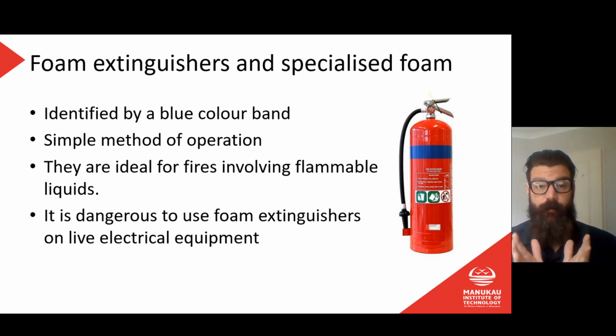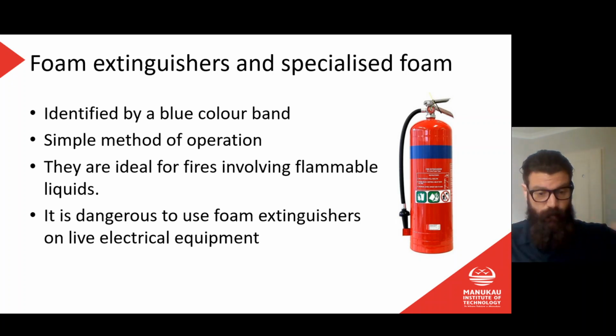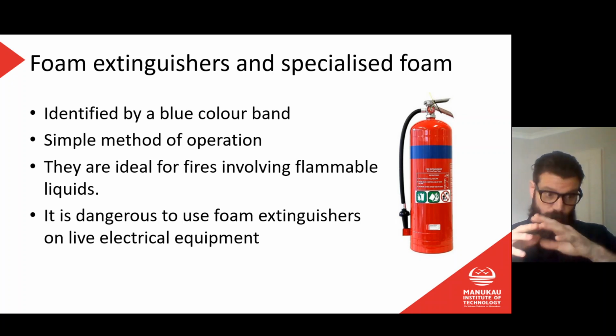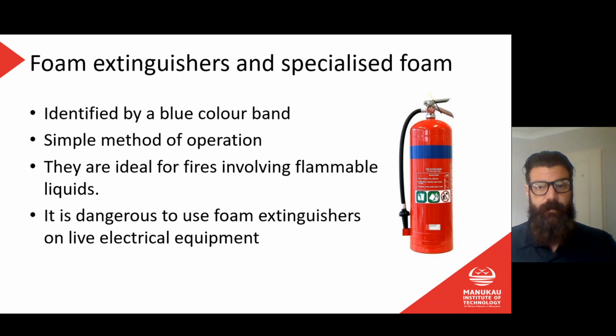The advantage of the foam over those other types of extinguishers is that the foam is quite light and it will sit on top without displacing a liquid. So you can spray it on top of an oil fire, and it's not going to shoot that fire everywhere or spread it like we saw with those other types. So foam ones are really good for flammable liquids. Again, it's dangerous with electrical equipment because that foam may be conductive, and therefore we don't want to do that. Once again, like with the dry powder, clean up on these ones is going to be a bit of a nightmare, although the foam does kind of dissipate.